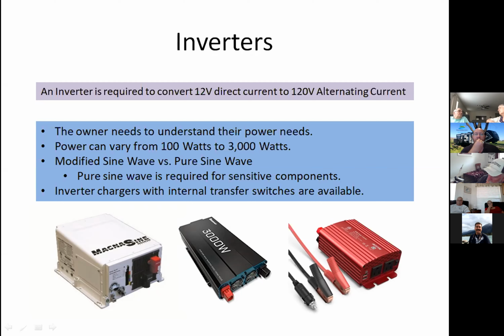It's important when selecting an inverter, if your budget allows, to go with a pure sine wave inverter instead of a square wave or modified sine wave inverter. This makes sensitive components like televisions and stereo systems run much smoother. There are also inverter chargers available with internal transfer switches - that Magnasine is typically an inverter charger, so you don't need a standalone converter to charge your system.